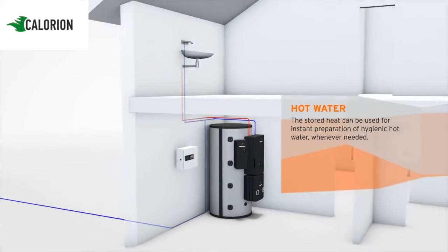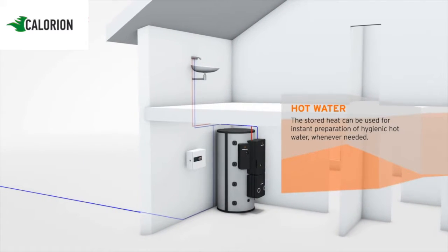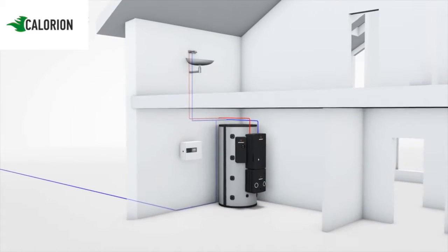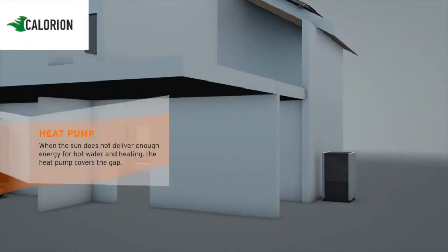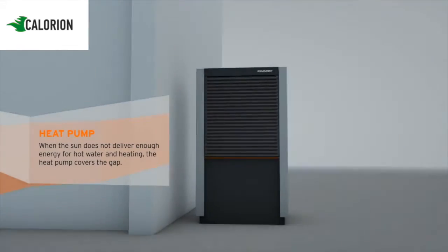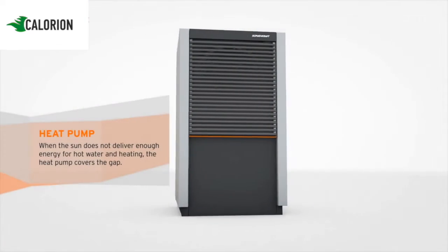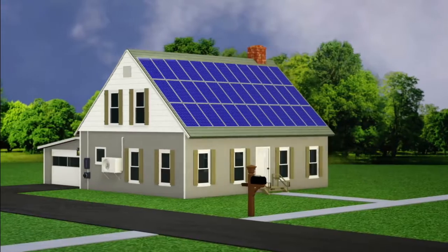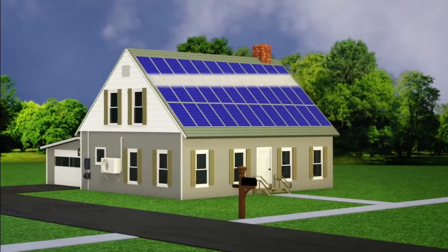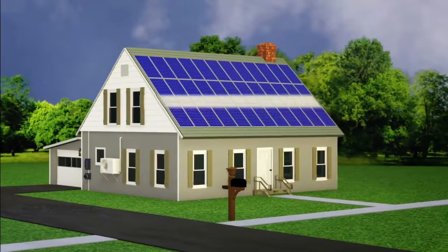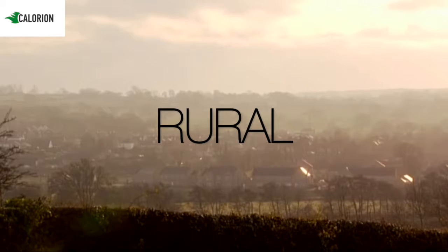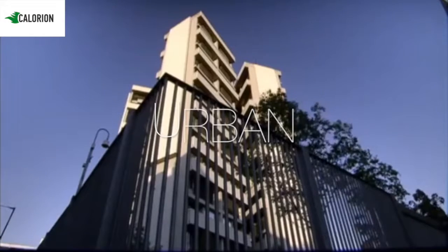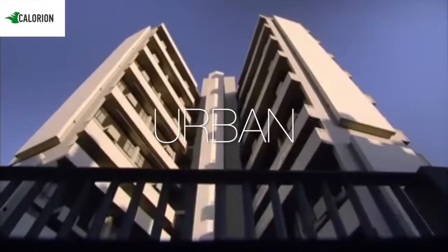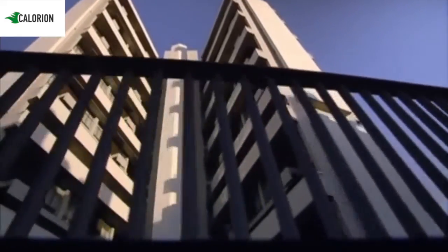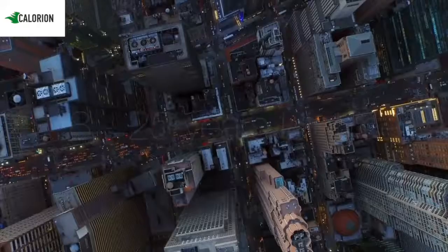The air source heat pump, thermal energy storage technology, and solar thermal energy account for 66.5%, 23.1% and 10.4% of total heating load respectively in a typical winter day, reducing the electricity consumption of the entire system by a third when compared to traditional systems like single heat pumps. These heat pump technologies can be implemented in both rural and urban areas. The suitable technique will be determined by us to ensure the most effective integration of the service.